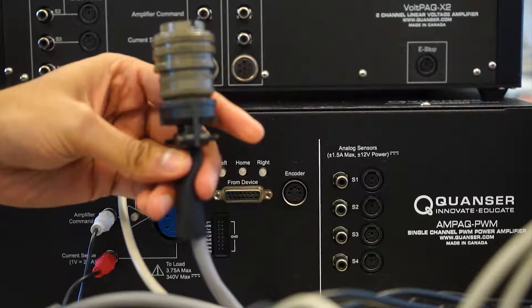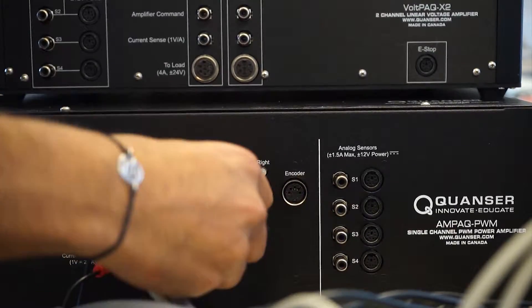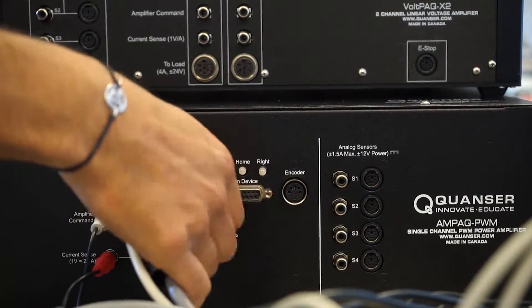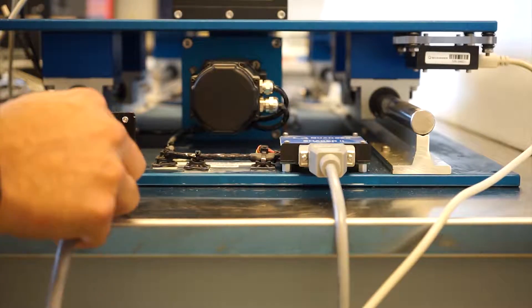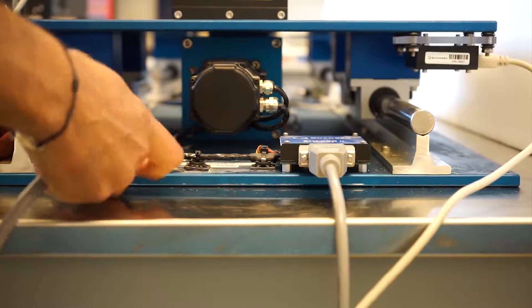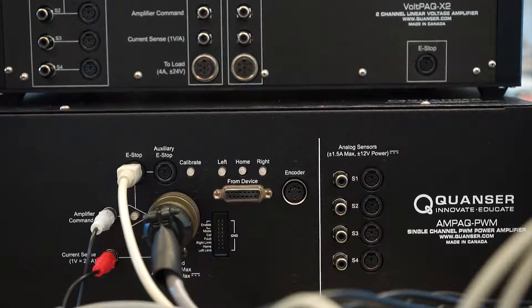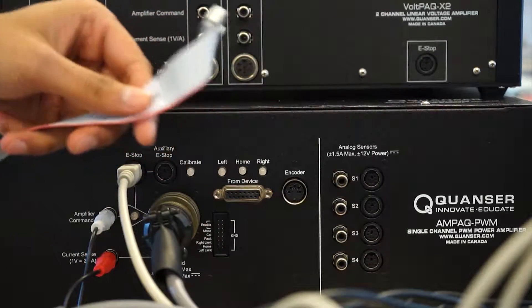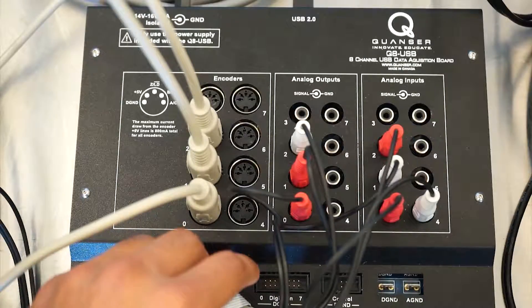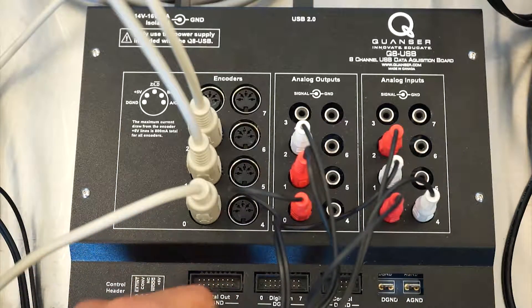Plug one end of the 4-pin Amphenol cable into the load port on the amplifier and make sure you tighten it securely. Next, plug one end of an RCA cable into the motor port, and then plug one end of the 16-pin I.O. cable into the amplifier, and then proceed to plug the two 8-pin digital in and out heads into the appropriate ports.